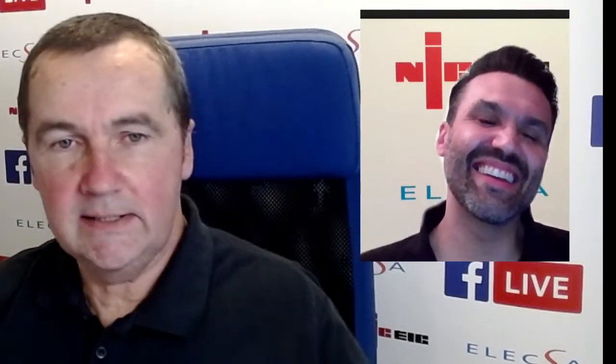Topical question. I'm going to try and answer it. Should all circuits be aimed to be covered by RCBOs as opposed to MCB split boards domestically usually? Okay, as we speak, split boards are still considered to provide a degree of division of installation, because ultimately that's what we're coming down to. There's a set of regulations around section 314 that talk about dividing the installation to minimise inconvenience in the event of a fault. Now, small installation, most typical domestic installations, you can actually get sufficient division to make sure that you've got a mixture, say, upstairs lights with downstairs sockets, or front of house lights with back of house sockets, so that you'll always have a power source even if you lose one half due to a fault.